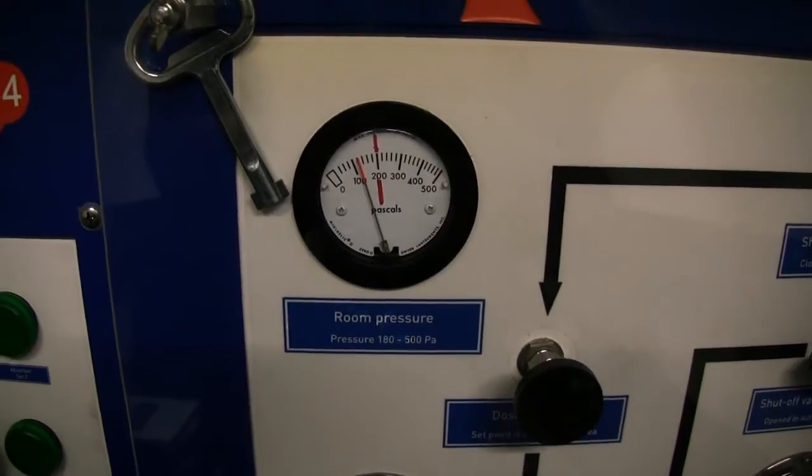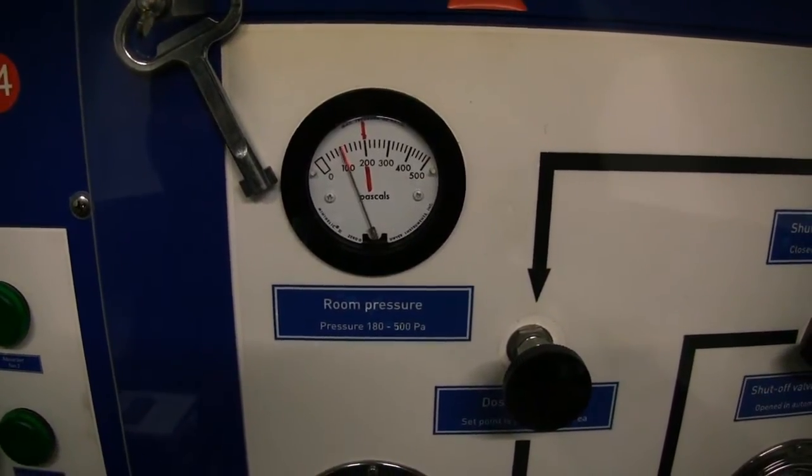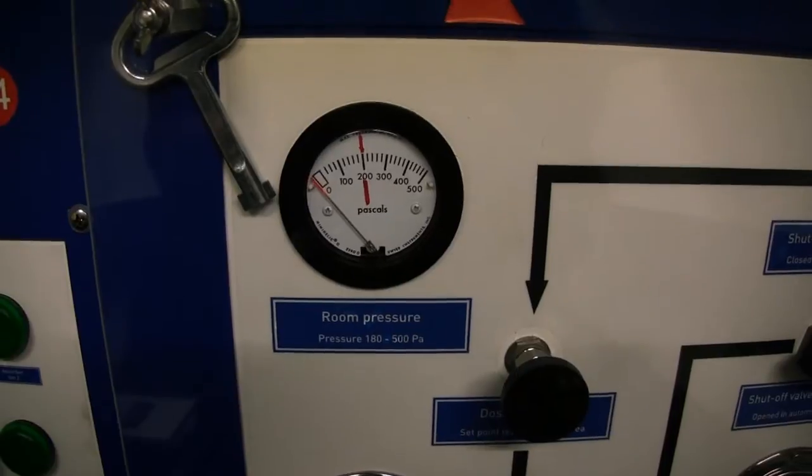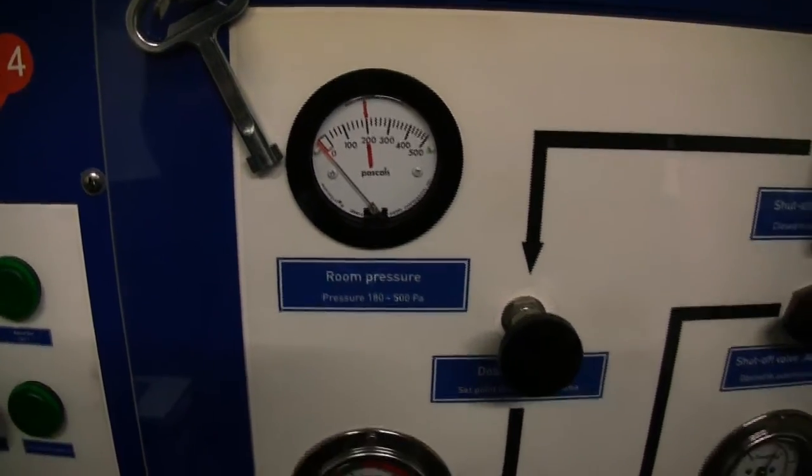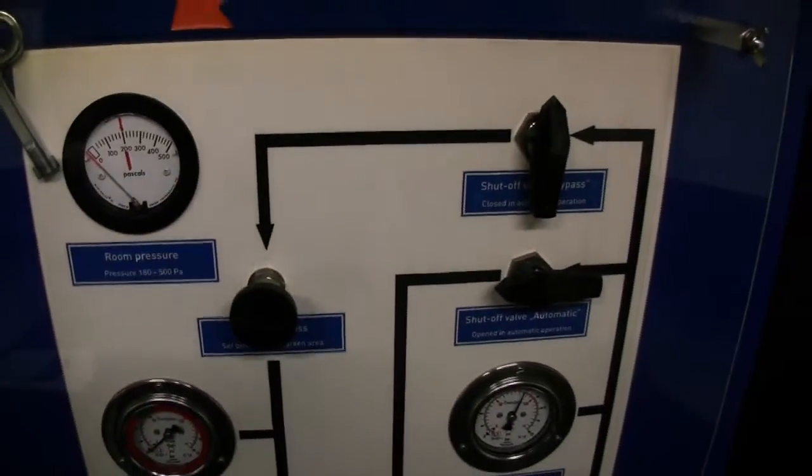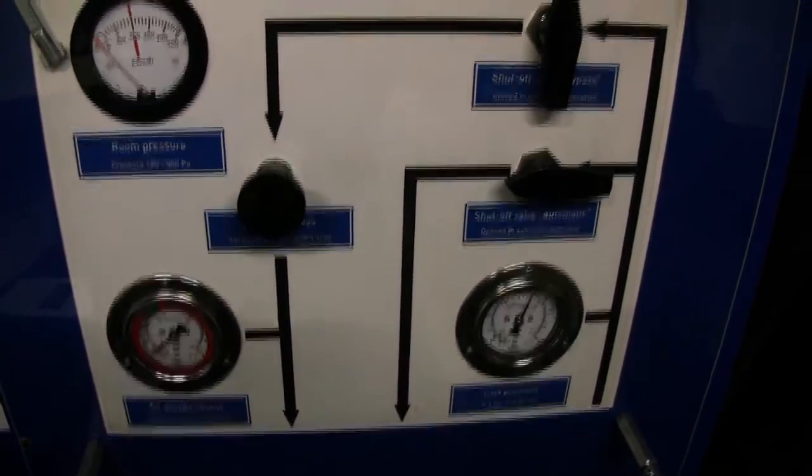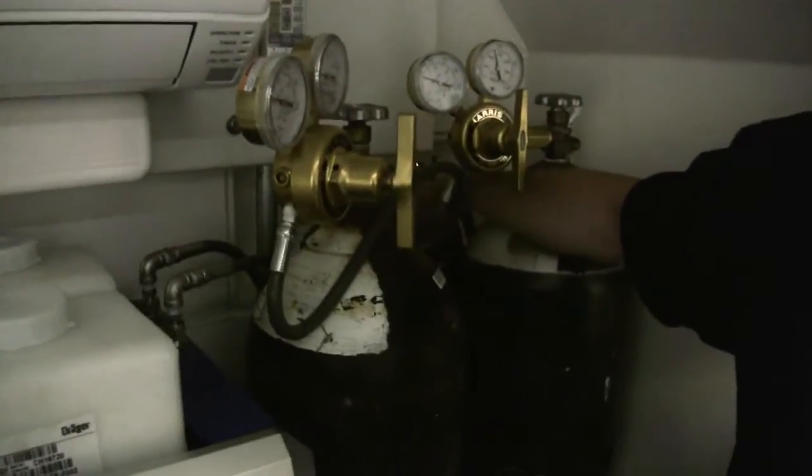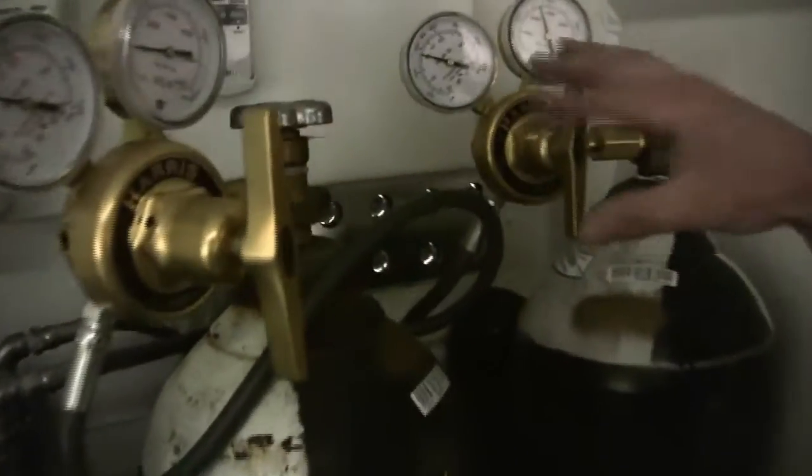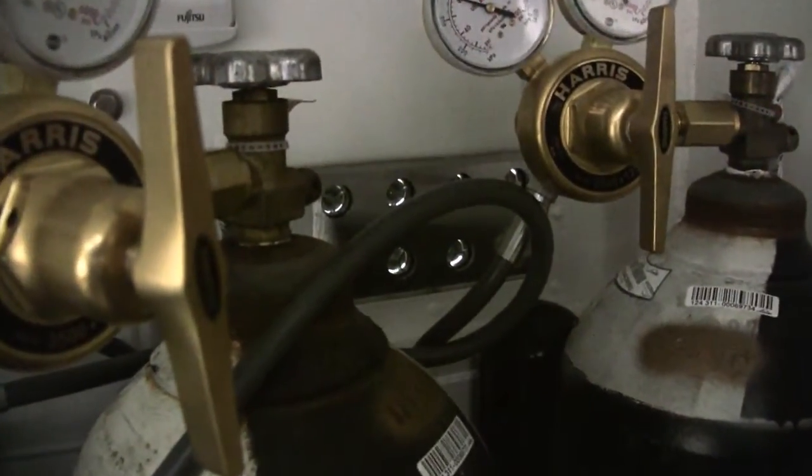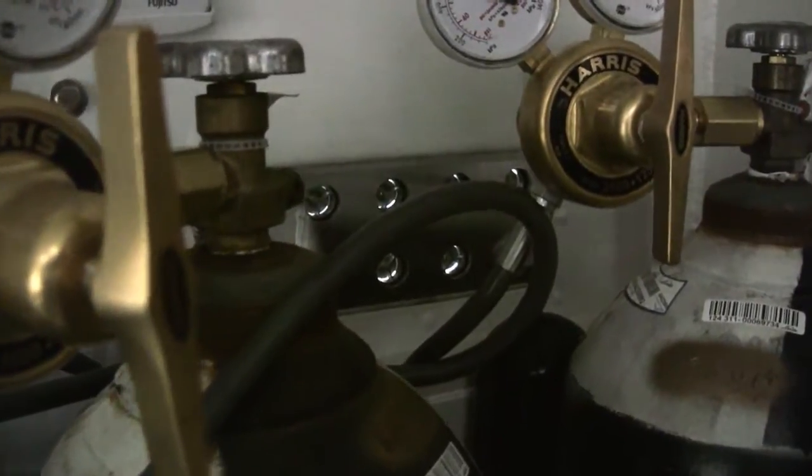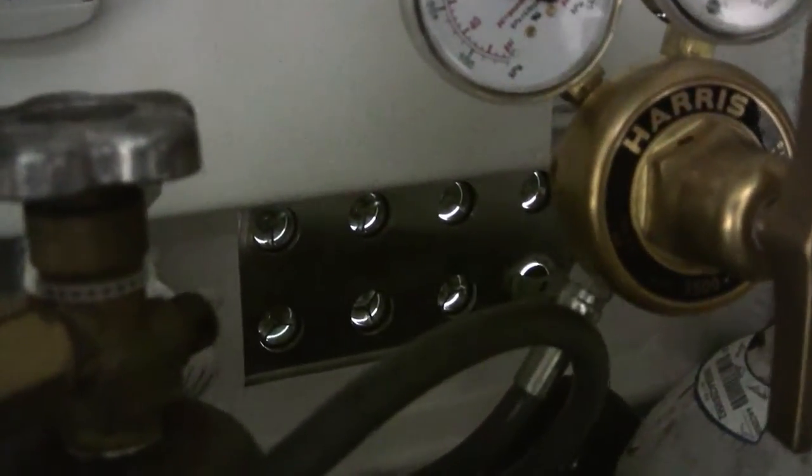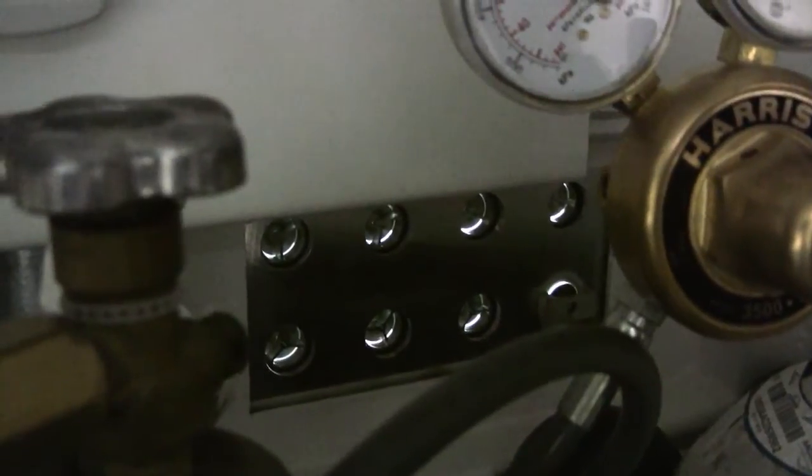So is there a safety limit on the number of Pascals or is it just a reference? A bandwidth reference. That's information. You can see it dropped out to zero. We open the door. What we have is pressure relief valves over here. At full air flow from the mine system these valves will all be open and purging constantly. That will hold your pressure to maximum. And we don't want it to go over 500. That's going to hold it about 400 Pascals.